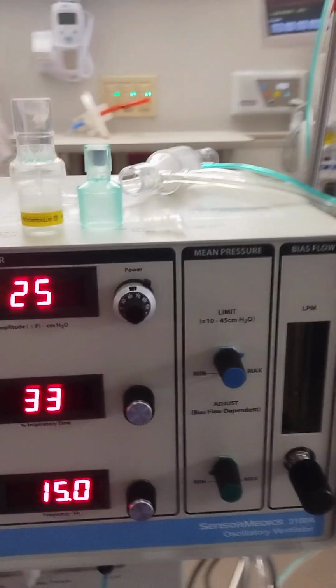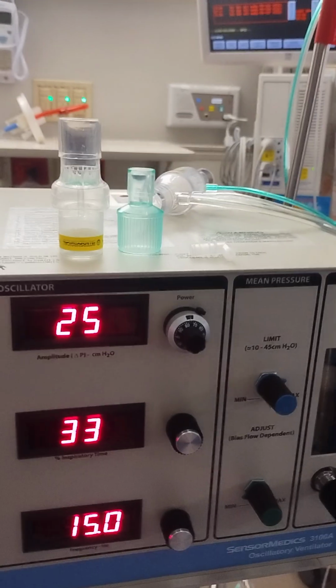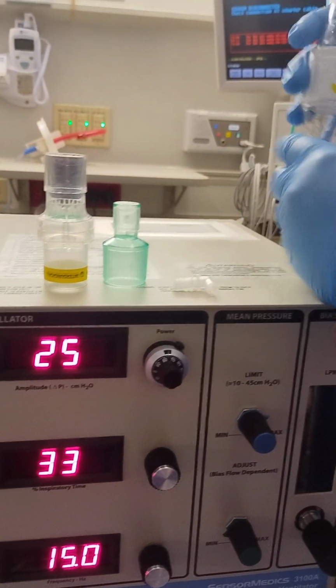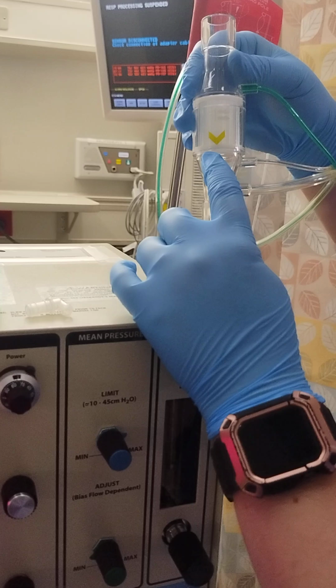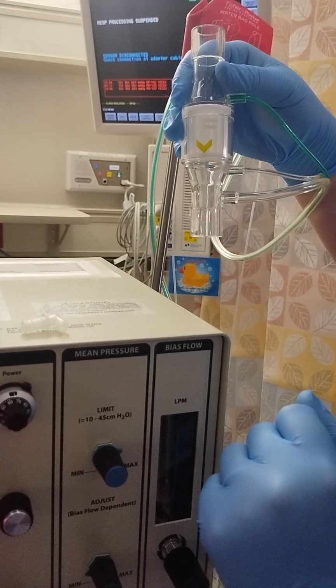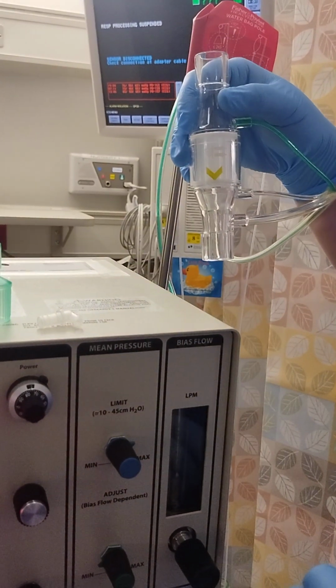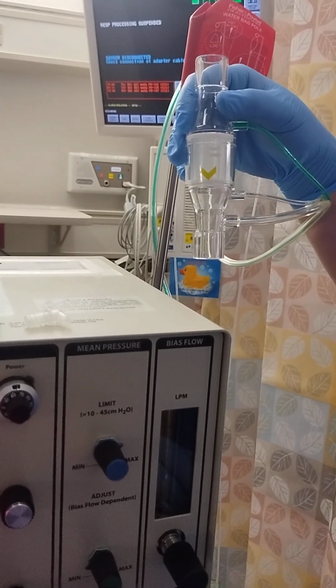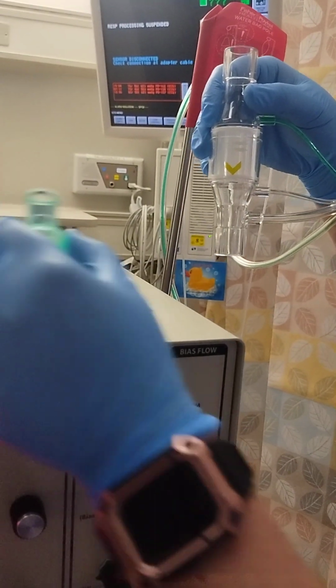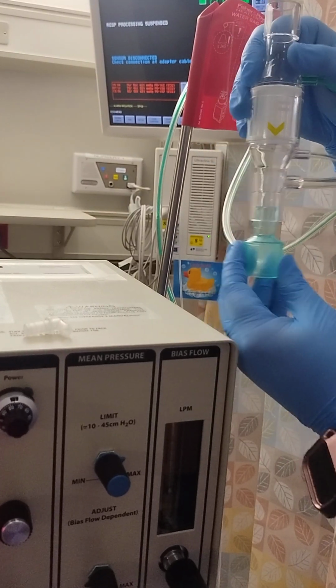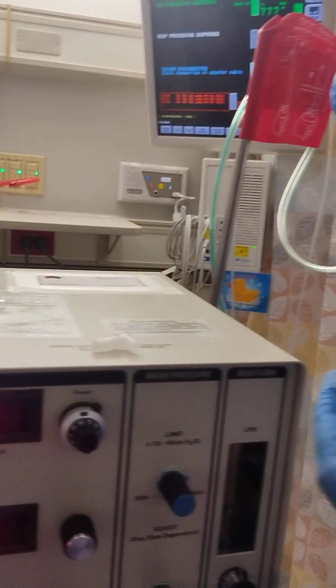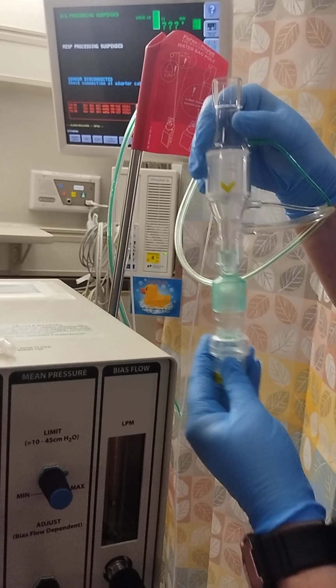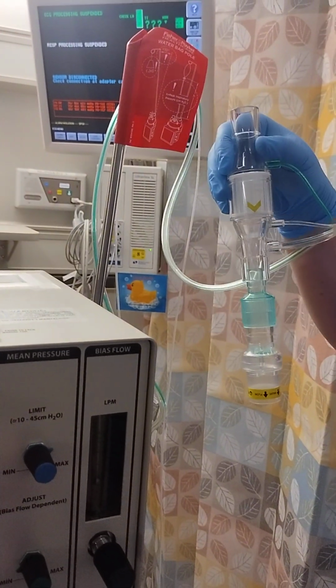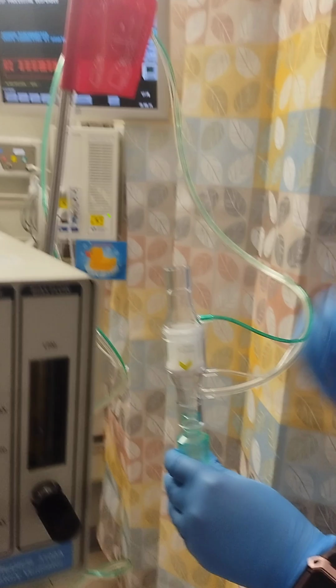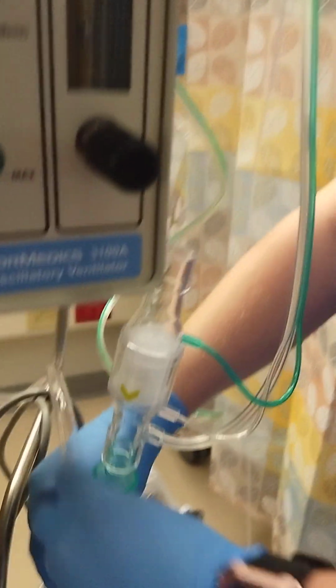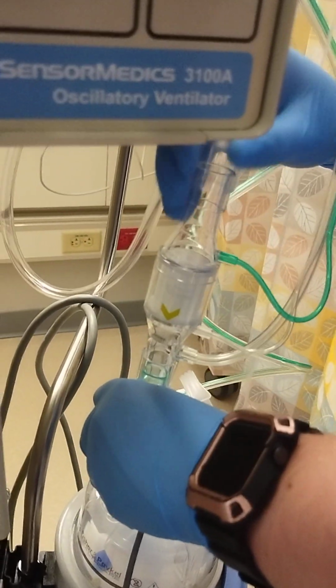So the first thing we're going to do is put these parts together, and you want the green arrow of your flow sensor to be pointing down toward your humidifier. We're going to be placing it on the dry side of the humidifier. We're next going to attach our green adapter, and then we're going to attach our one-way valve because we're putting it on the oscillator. Now if we weren't putting it on the oscillator, we would not need that one-way valve. So here we're going to go ahead and quickly take it off.